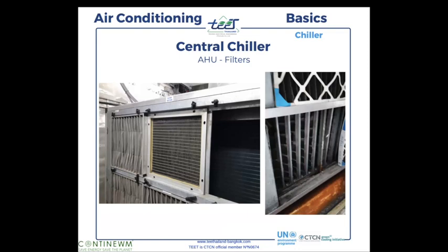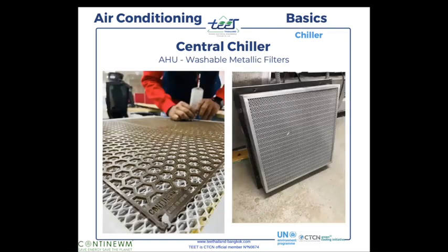You may have multiple layers of filter. In this case, you have the first filter, the preliminary filter, and the secondary filter. Okay. Here as well on the right side, you have a preliminary filter, that is a fiber filter, and a secondary filter, that is a bag filter in this case. Okay. But always behind you have the coil. Here you have the coil, and here we cannot see it, but it's behind the bag filter. This is just to show you so you are not surprised when you visit.